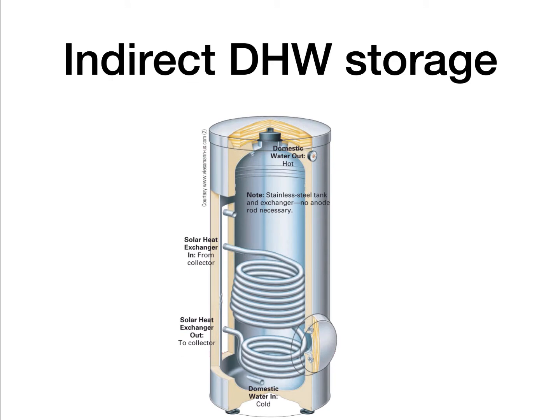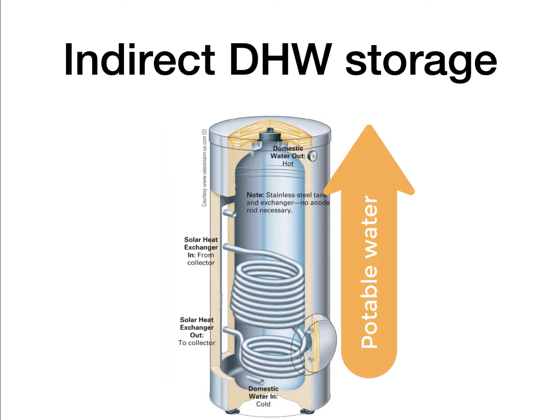Depicted is a typical indirect domestic hot water storage tank. It has a large volume storage tank that varies between 40 and 119 gallons, and it has an internal immersed coil through which closed loop hot water is circulated. It can be used as a solar domestic hot water preheat, but is more commonly used with a boiler as its heat source. Note that the heated water enters through the top of the heat exchanger and the less hot water comes out of the bottom, while the cold water enters the bottom of the storage tank and the hot water exits out of the top. This is basically a counterflow condition that extracts the maximum amount of heat available from the heat source.